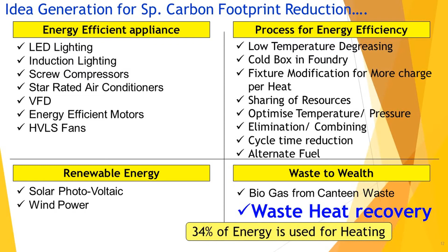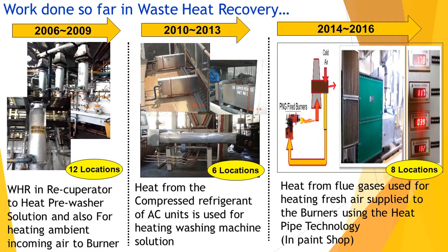The waste heat recovery subject is not new to us. In the past, we had put recuperators on the heat treatment furnaces to recover heat and use it for the preheater washer. Similarly, we recovered heat from the heat of compression of refrigerant and used it for the washing machine solution. We have even recovered flue gases going from the chimney; with heat pipe technology, we could extract the heat and use it for heating the ambient air for the burners.